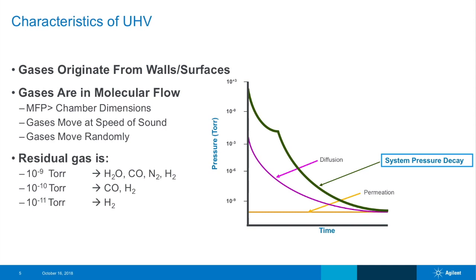The gases in a UHV system are in molecular flow — the mean free path is much greater than the chamber dimensions, meaning particles have no interaction with each other and only interact with the chamber walls. They move at the speed of sound, roughly 750 miles per hour, moving randomly in all directions in straight lines. Even at 10⁻⁹ torr, we still have water, carbon monoxide, nitrogen, and hydrogen coming off surfaces. At 10⁻¹⁰, we're really looking at carbon monoxide and hydrogen. In true UHV — what people now call XHV — down at 10⁻¹¹ torr and lower, the only species remaining is hydrogen.